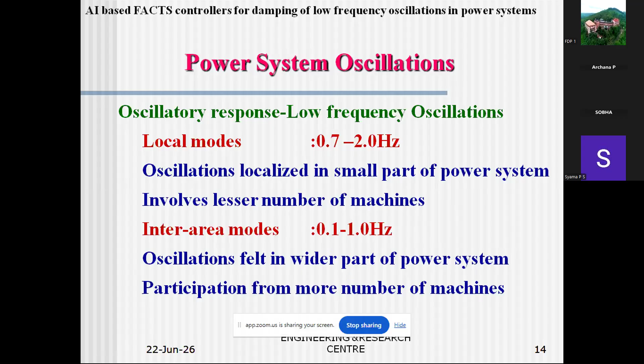Even though both are expected to operate at 50 hertz, there could be some oscillatory behavior, and this can result in some modes in this particular range. Then we can say that there is an inter-area oscillation with respect to these two systems, that is, the Kerala grid as well as the Tamil Nadu grid. That means more machines are involved, participation from a larger number of machines, and oscillations will be felt in a wider part of the power system. So these are the different modes of oscillations, that is, local modes and inter-area modes.